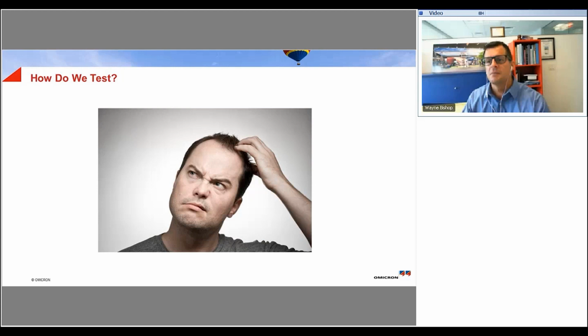So that begs the question, how do we go about testing, right? If it's so complex, how is it done in the world? When testing a DA scheme with communication or distributed logic, the test needs to include all the protection devices in the scheme in order to verify their correct functionality. A DA scheme can be implemented with hundreds to thousands of lines of custom code or custom logic for both the recloser control itself as well as any kind of automation controller. So prior to a scheme being deployed in the field, it needs to be thoroughly tested to ensure that it operates as expected, especially when put into operation. When a fault occurs, the DA scheme needs to identify and locate the fault, and figure out the best way to clear the fault and restore the unfaulted line segments through various switching sequences. These switching sequences also need to be tested to fully verify the functionality of the scheme.